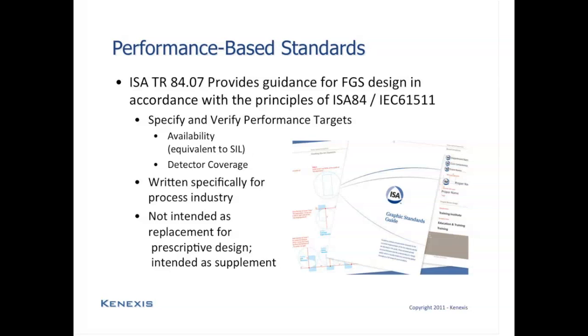But in essence, what the ISA 84 Working Group 7 came up with in a technical report is that a fire and gas system can be designed quite similarly to an SIS if an additional consideration is made during the design. So instead of just assigning a SIL target or a safety availability to the loop, it is also important for a fire and gas system to specify the detector coverage. So the determination and quantification, verification, and validation of the detector coverage is going to be required when using a performance-based fire and gas system design, in addition to looking at the SIL target or specifically the safety availability target.